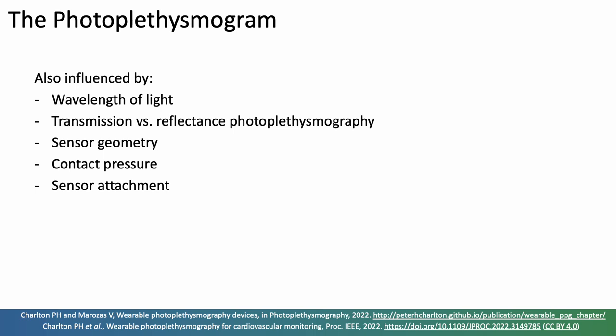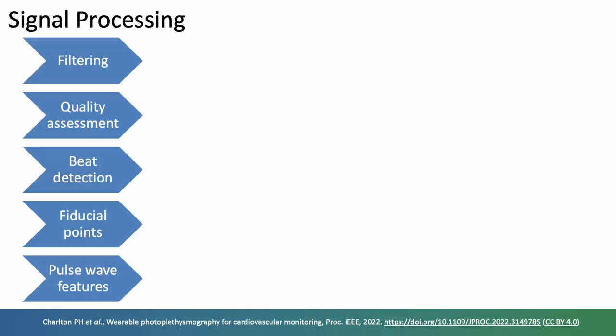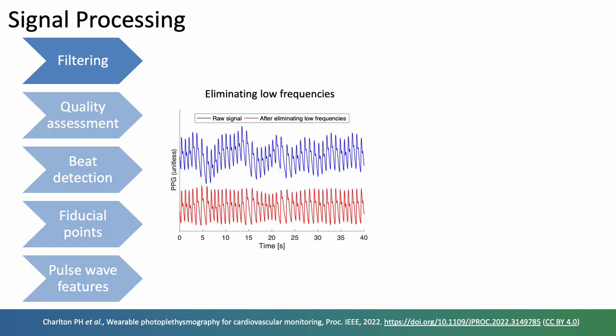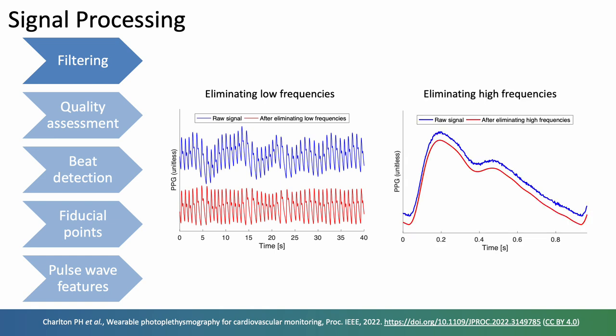Having obtained the signal, the next step is to process it, and I'll take you through the five steps which are traditionally taken to process PPG signals. Firstly, the signal is filtered to eliminate unwanted frequency content. Low frequencies are eliminated, so here we go from the raw signal in blue to the red signal where low frequencies have been eliminated, and also high frequencies are eliminated, here zooming in on one pulse wave.